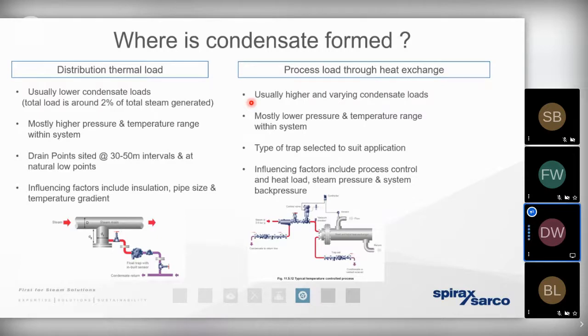But in the first hour or so, if we're warming a steam system up from cold, more and more of the steam is going to give up its heat energy to the infrastructure itself, even before it gets to the process. We refer to that as the warming up load. So we always double that warming up load to allow for the greater mass of condensate that will need to be removed from the network when we're bringing it up to temperature. So that 200 kilograms per hour running load will become 400 kilograms per hour warming up load. And that's what we want to size the steam traps on.